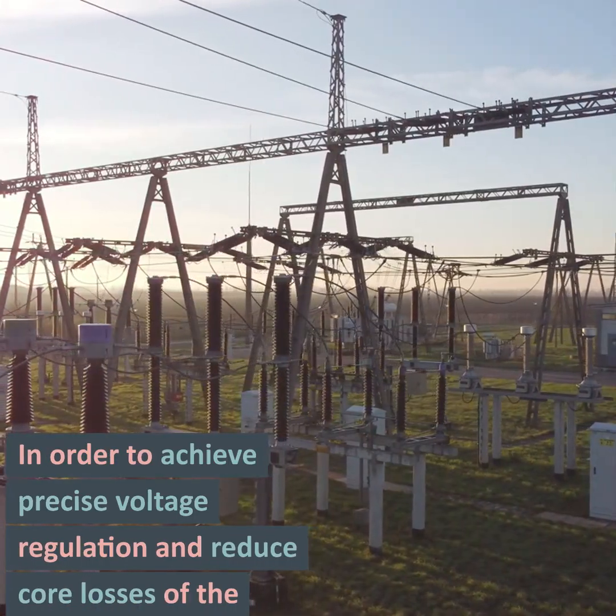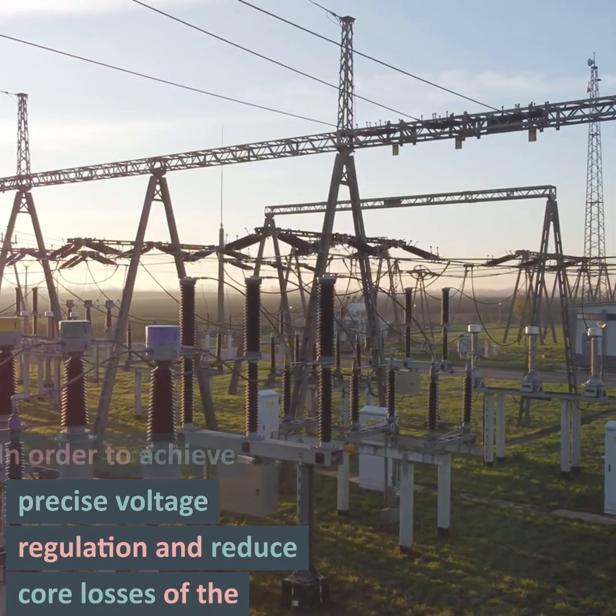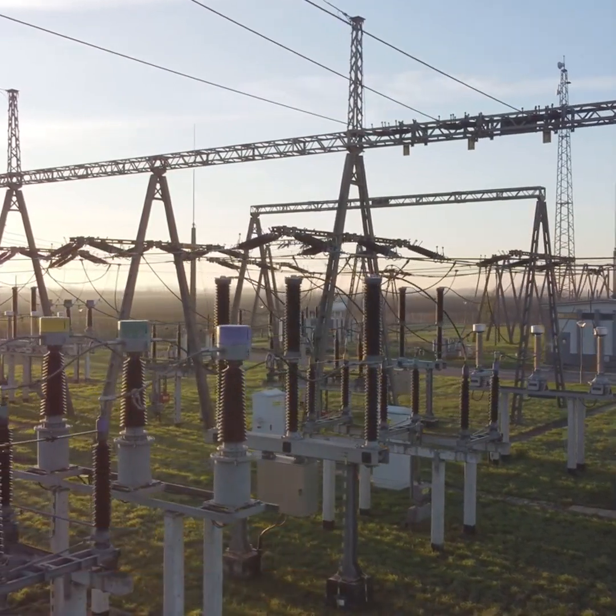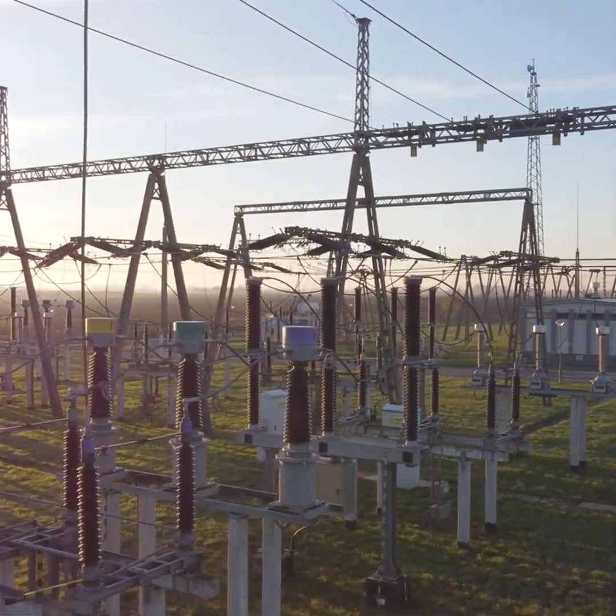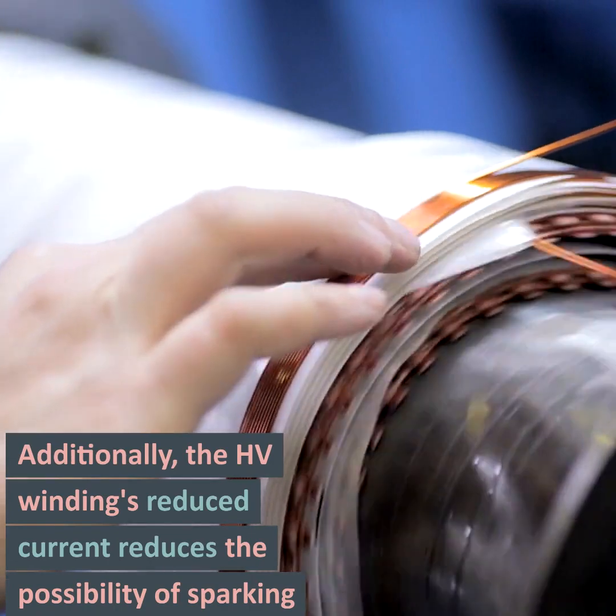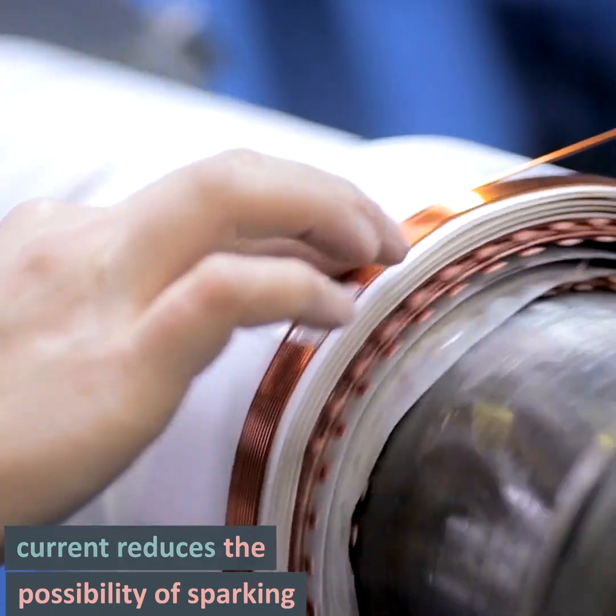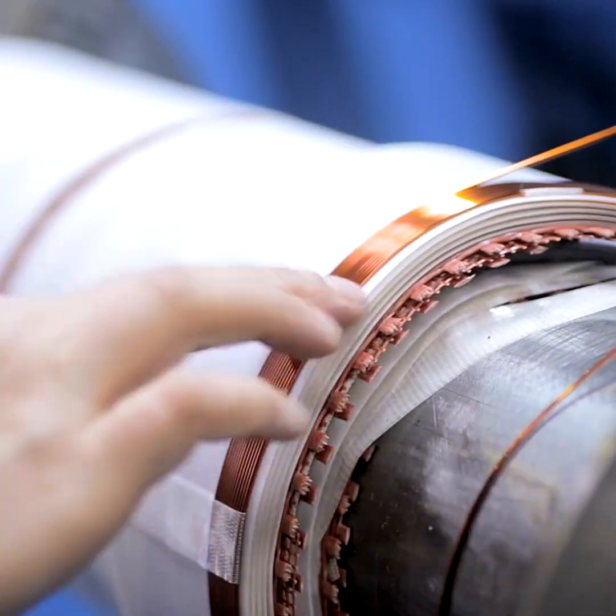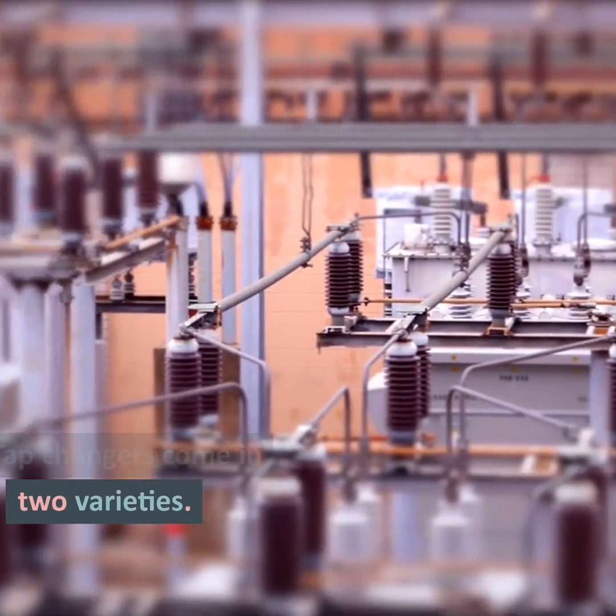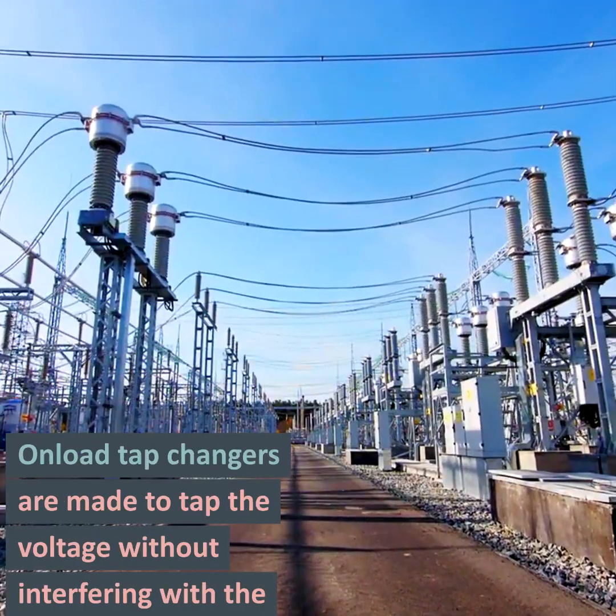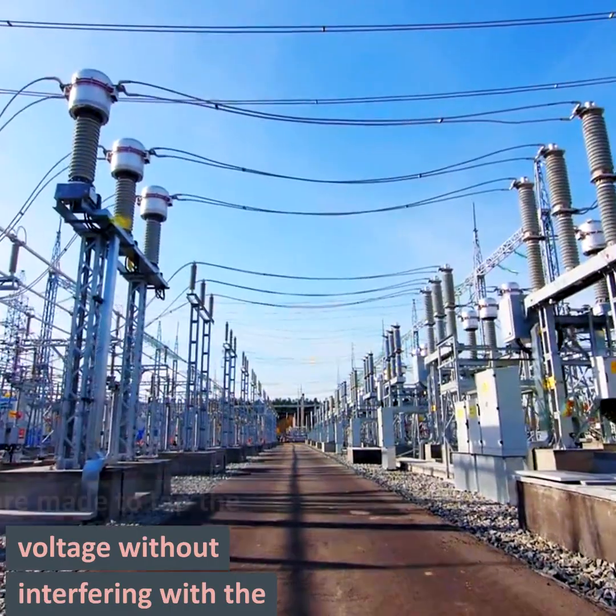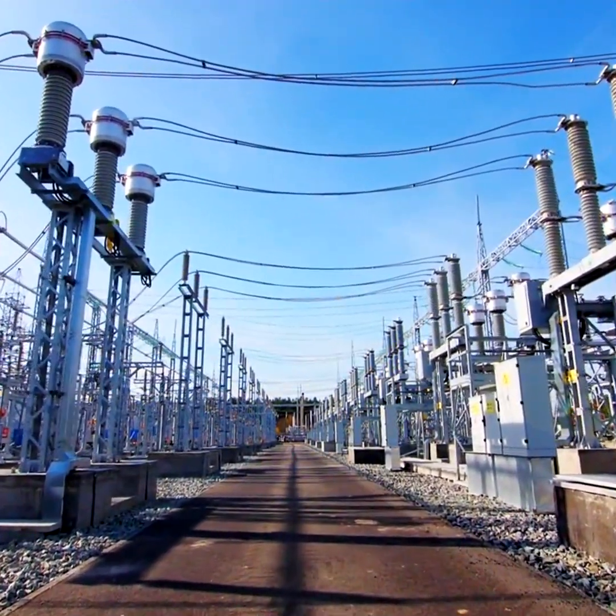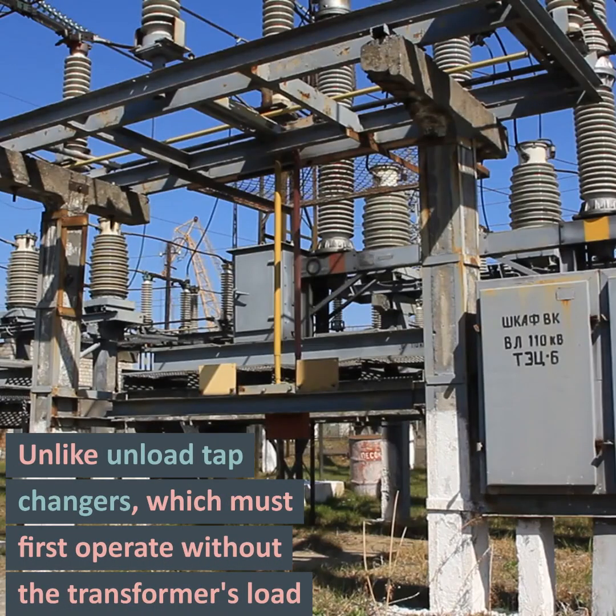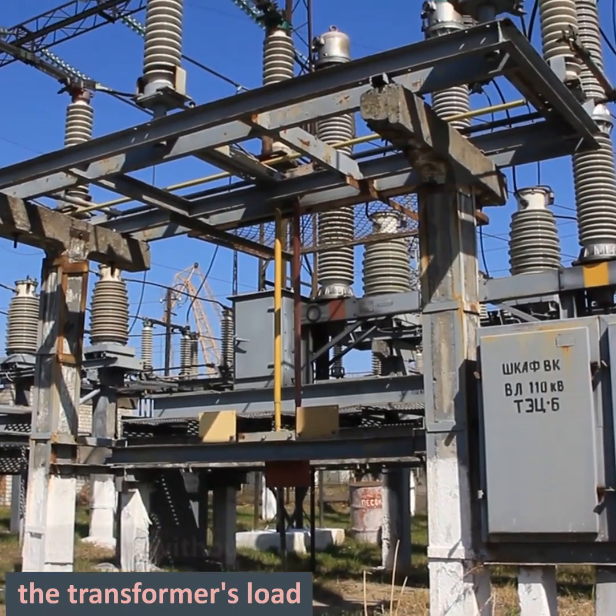In order to achieve precise voltage regulation and reduce core losses of the transformer, tap changers are frequently attached to the HV winding. Additionally, the HV winding's reduced current reduces the possibility of sparking and igniting the transformer oil. Tap changers come in two varieties. On-load tap changers are made to tap the voltage without interfering with the passage of current to the load. Unlike off-load tap changers, which must first operate without the transformer's load.